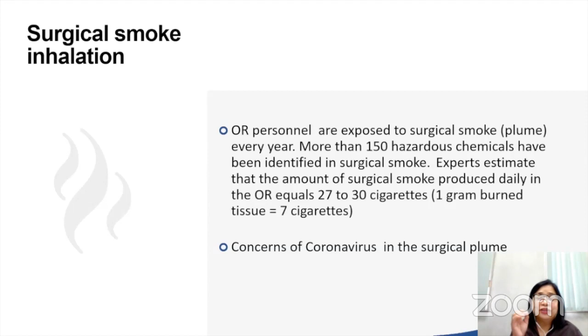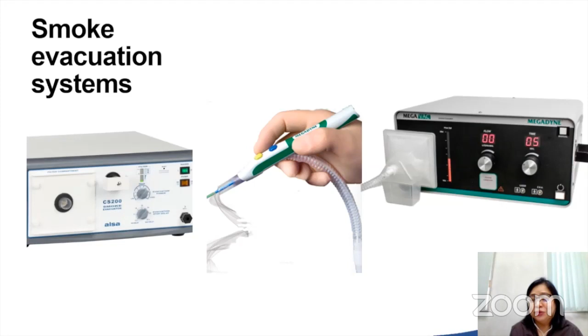Now, because of concerns of coronavirus surviving in the surgical room, it's even more important now to suction that air or that smoke during the surgery. What we have now are smoke evacuation systems, which is a very simple device, but it's very helpful, where the suction and the cautery are kept together in one device so that as soon as you burn tissue, there's smoke generated, it is automatically suctioned out into a closed suction system so you don't get to inhale. So the dictum is don't inhale.